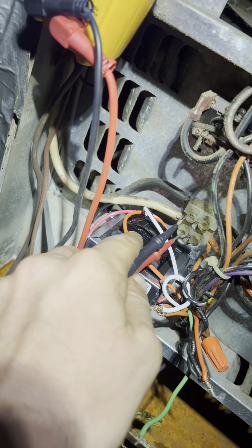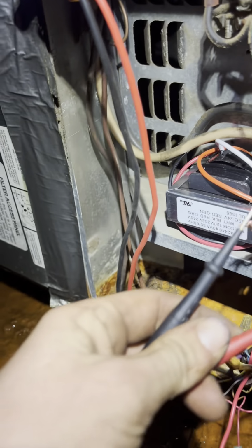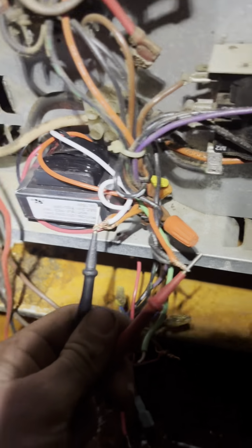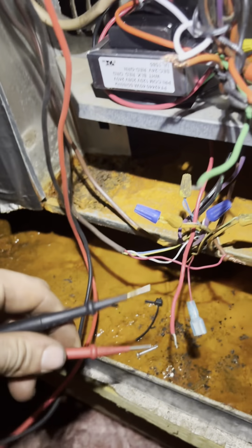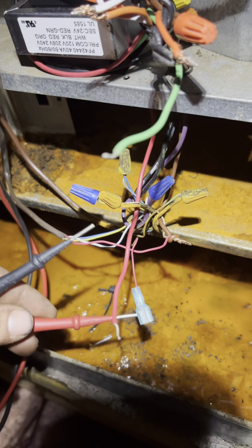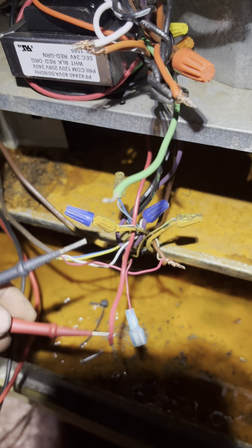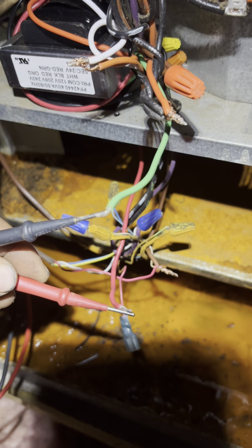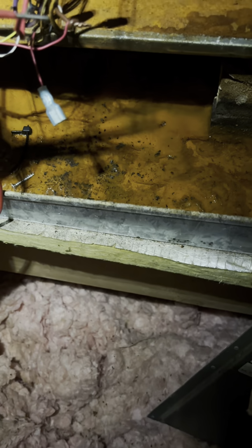All right, y'all, let's see where we're missing voltage at. I've got voltage right there. That's the two legs right there coming off. I've got voltage right there. So I should have 24 volts between this red and this green right here. Let's find out. It's hard trying to do this one-handed. All right, I got them touching now, and I do not have voltage. So that tells me that that transformer right there is bad.